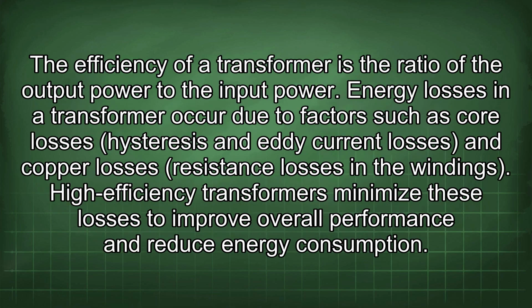The efficiency of a transformer is the ratio of the output power to the input power. Energy losses in a transformer occur due to factors such as core losses, hysteresis and eddy current losses, and copper losses, resistance losses in the windings. High-efficiency transformers minimize these losses to improve overall performance and reduce energy consumption.